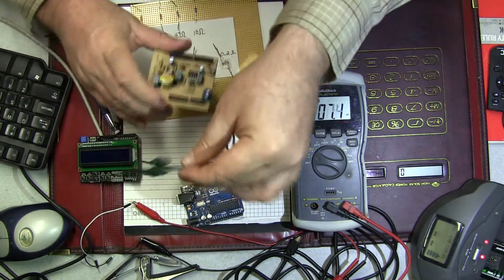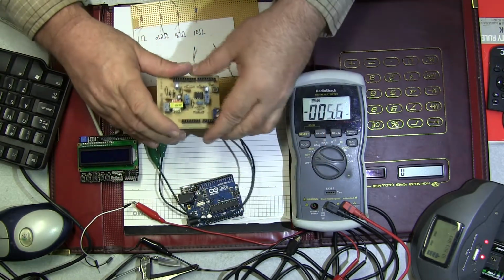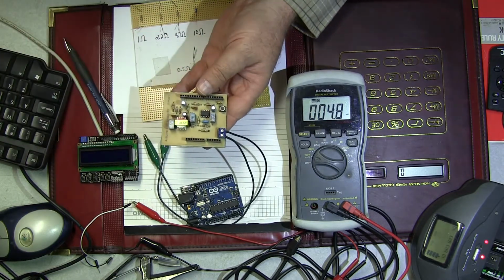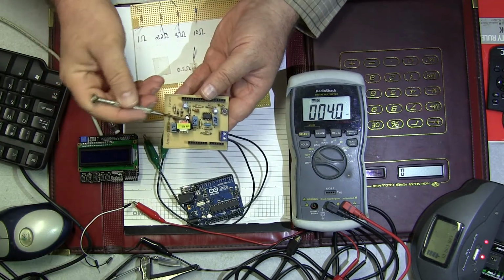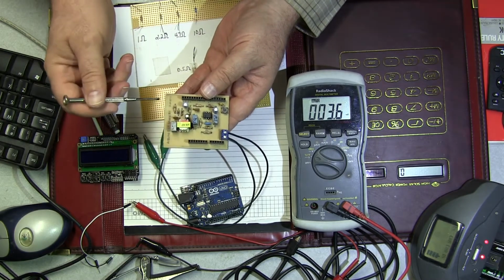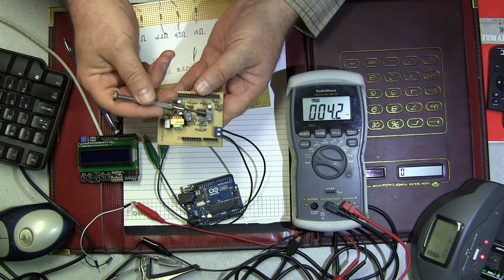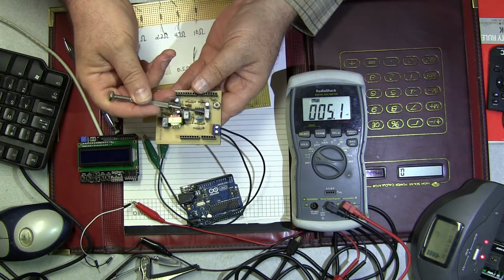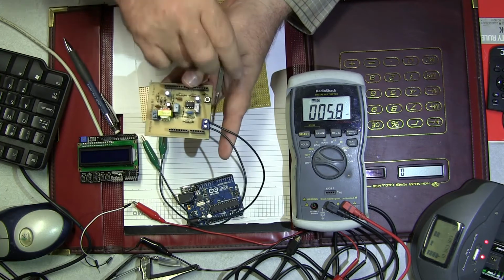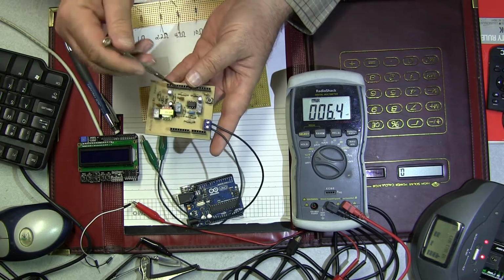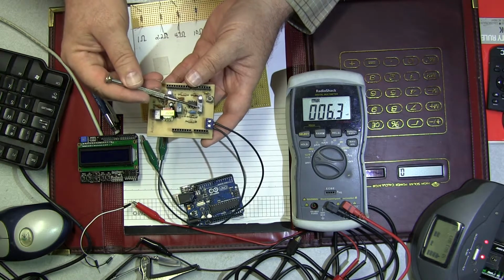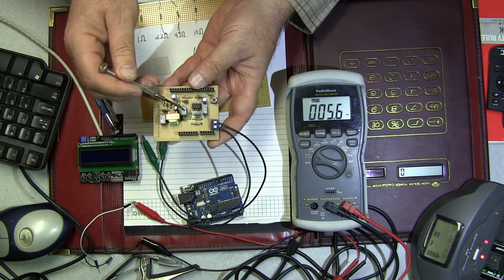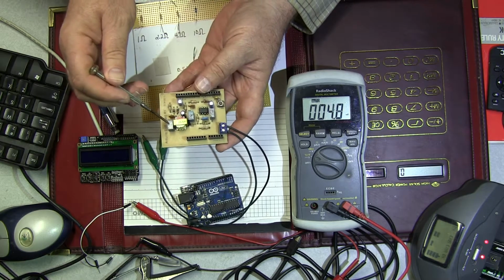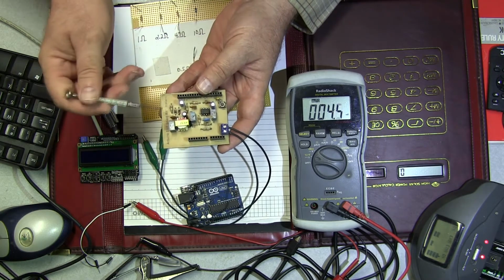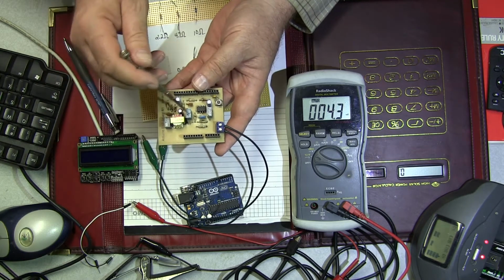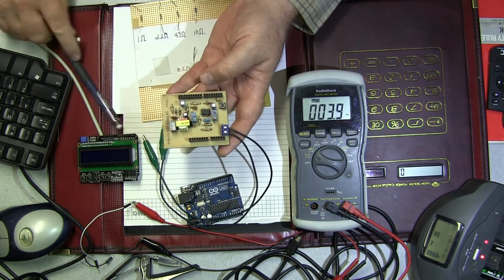And hook up your lead wires. And you'll see on mine, I have put labels on the top of my pot just to make it easier for me to see. The first pot I have here is the attenuation pot. This just attenuates the signal coming back out of that capacitor that you're measuring. This is R5. The frequency adjustment, that's R6. And then the load potentiometer, the span, or whatever you want to call it, that's R9. So just label those. It makes it a little bit easier in the setup to follow along.